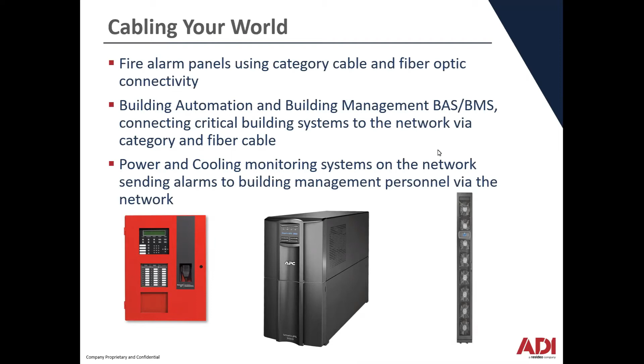In the fire alarm space, we're seeing more category and fiber optic cable used to connect fire alarm panels in large systems - you may have a main fire alarm panel at the main building, then throughout the campus connect all your downstream alarm panels via fiber optic or category cable. Other devices we're seeing networked these days, and this isn't new, are UPSs and in-row cooling units - alarms can be set when power goes off or there's a cooling situation. These are definitely devices that need cabling, and there are more products in that space than in the past.